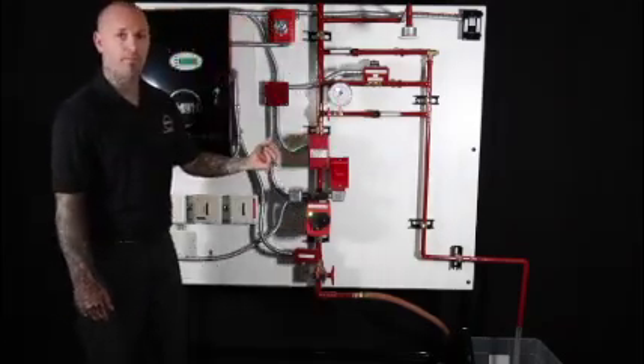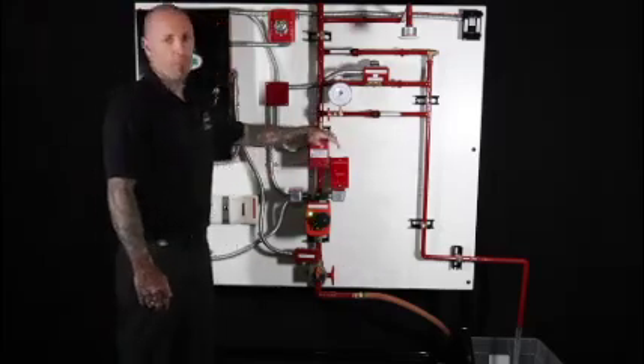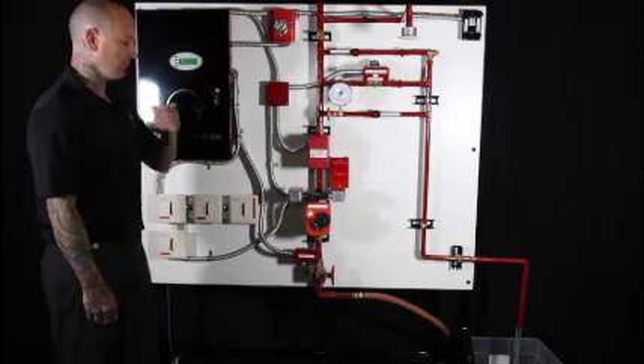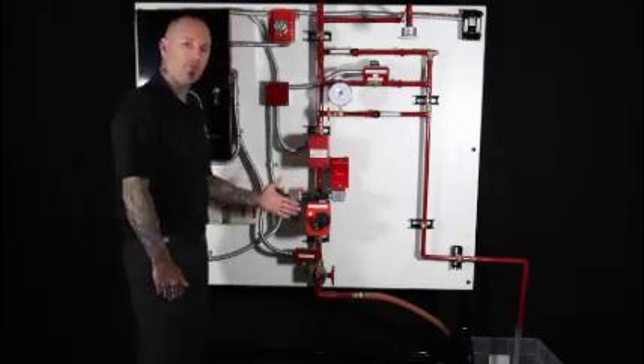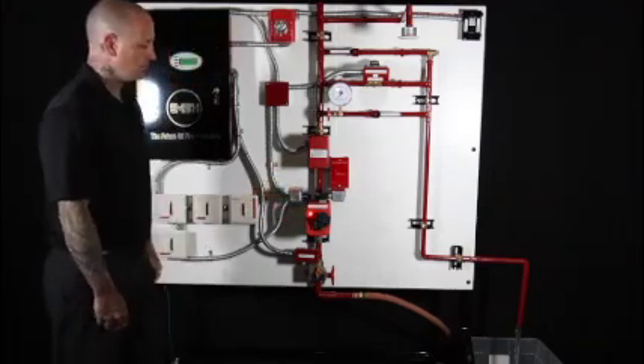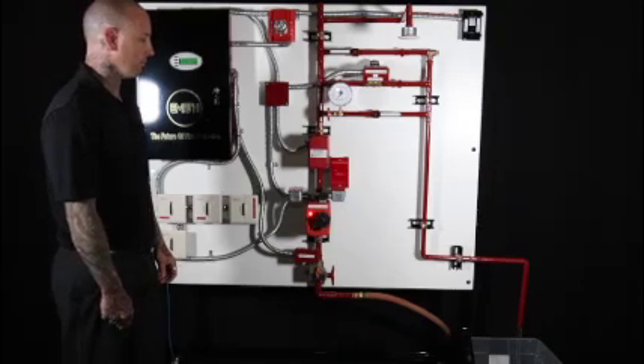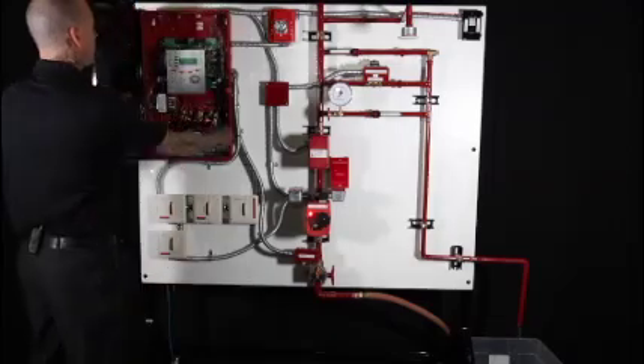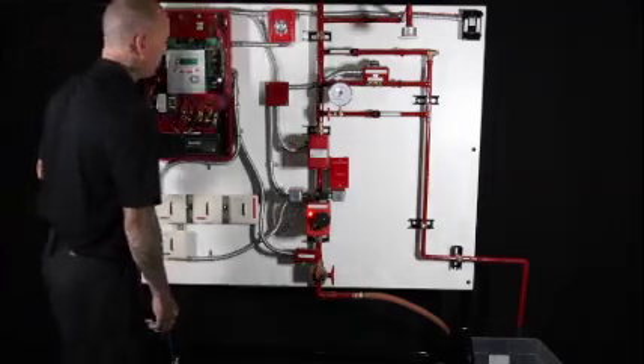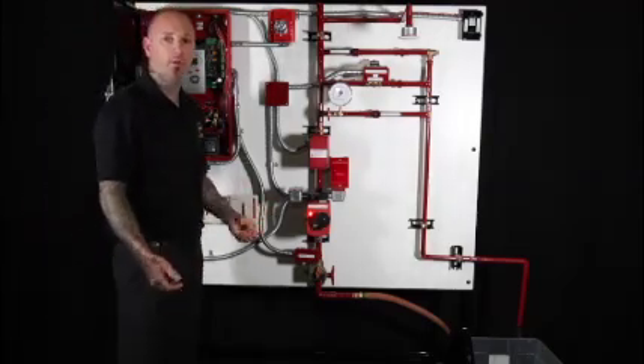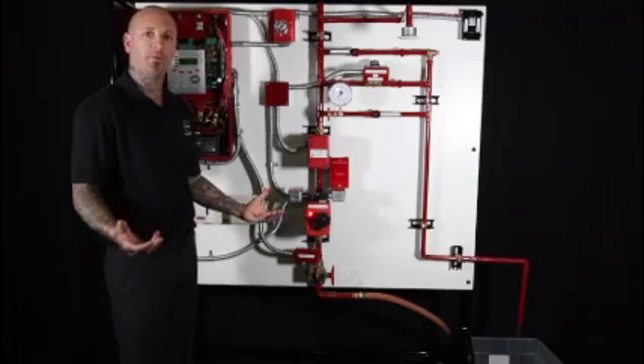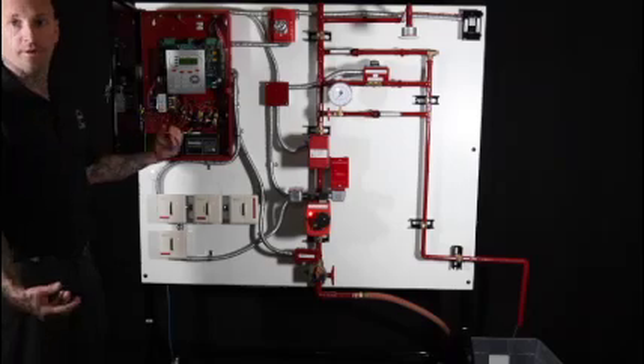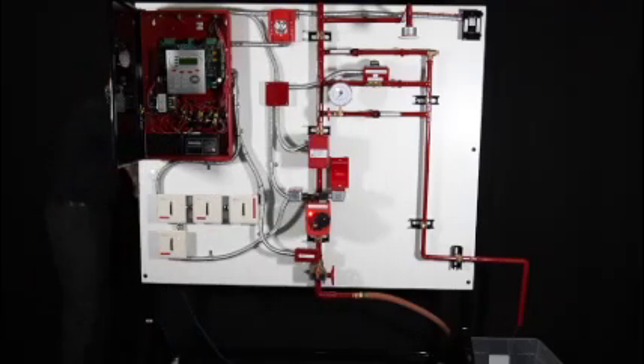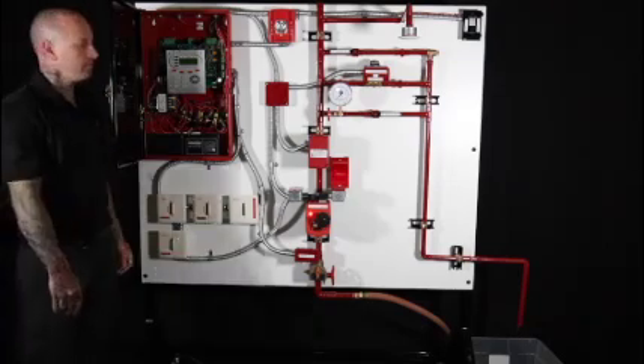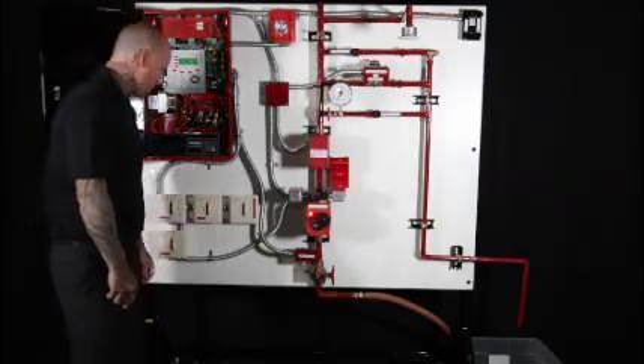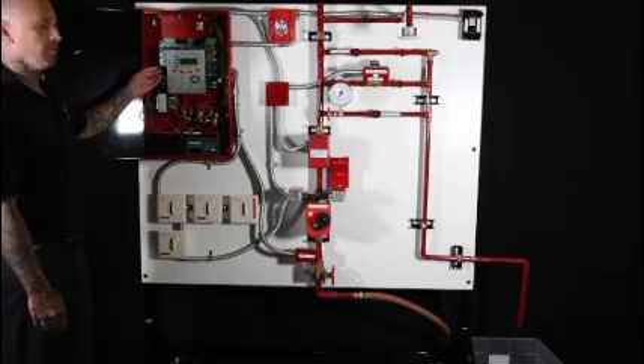We have a broken sprinkler pipe. Water starts flowing, and the flow switch goes off. It'll now shut itself down. And we'll silence that alarm. So now I'll take the power off the system as if there were a lightning strike, power failure, or something happened, and the alarm system will detect it. Shortly after your loss of power, you're going to get an alarm signal in the alarm panel.